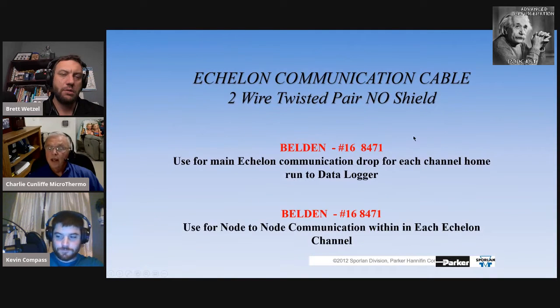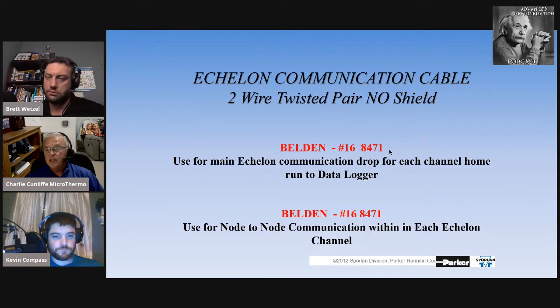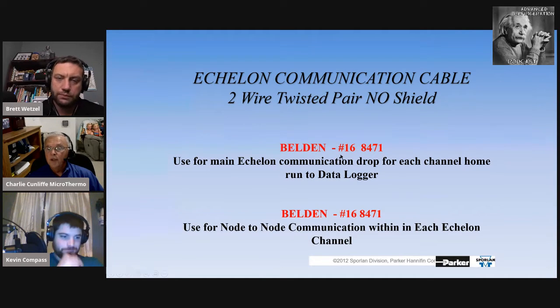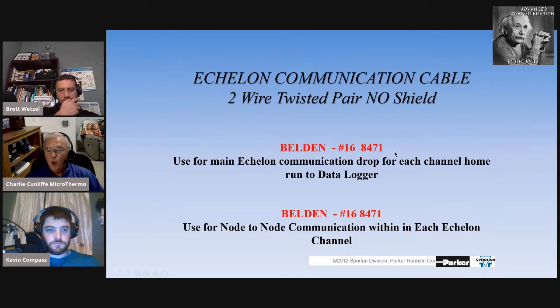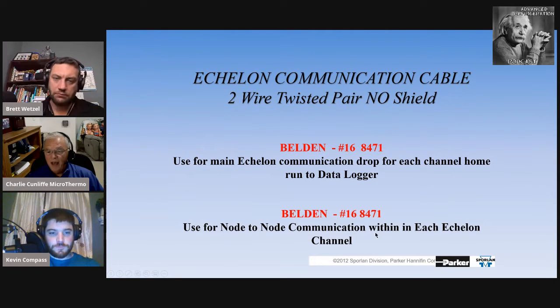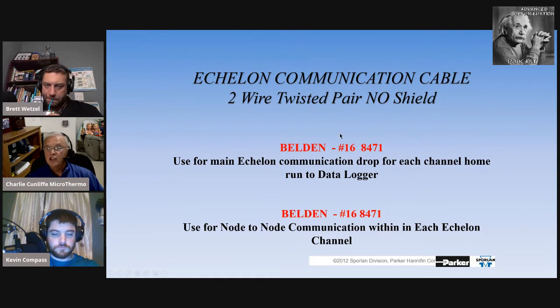Okay, cool. Here's a biggie with the Echelon network, and if I harp on this, I apologize. I'd prefer you use the Belden. I almost guarantee that if you use the Belden 16 gauge 8471 for both your main drop and your node-to-node communication, you will not have a problem with an Echelon network. It's 2-wire twisted pair, no shield whatsoever, 16 gauge, which is heavy duty for communication wire, and a minimum of 6 twists per foot. So it's the twist that actually creates like an EMF shield on the wire.